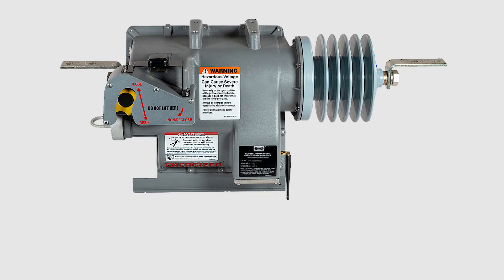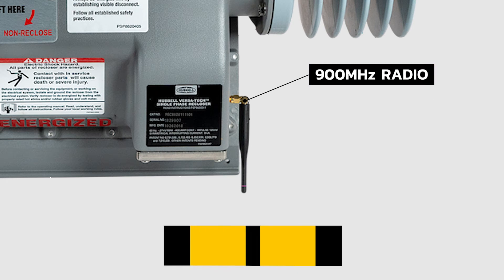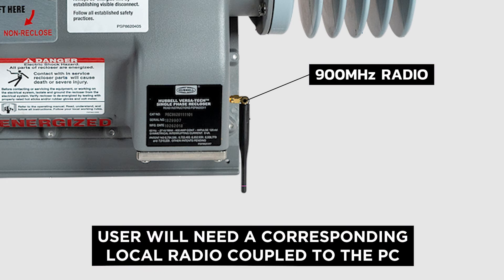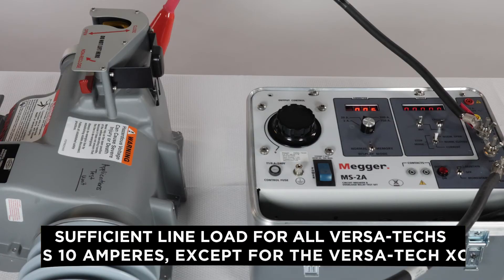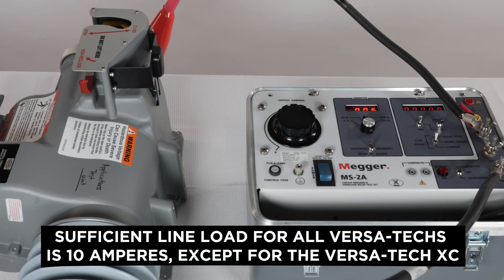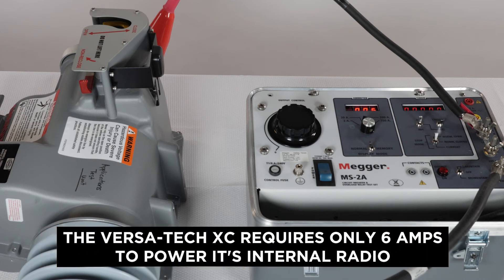To connect to a Versa-Tech that has an internal or external 900 megahertz radio, the user will need a corresponding local radio coupled to the PC. To power the wireless 900 megahertz radio on the Versa-Tech recloser, either sufficient line load or an internal battery will need to be used. Sufficient line load for all Versa-Tech reclosers is 10 amperes, except for the Versa-Tech XC, which requires only 6 amps to power its internal radio.